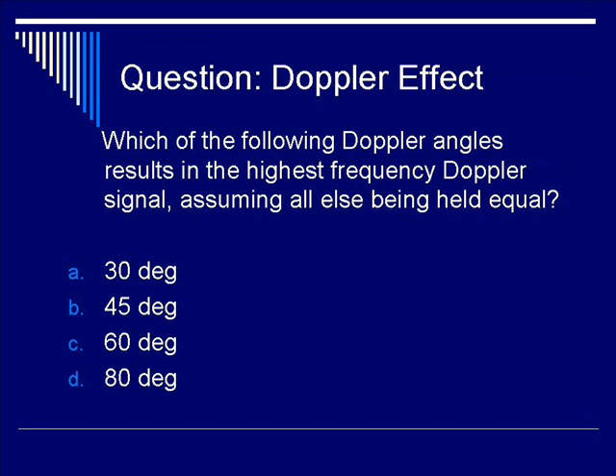Let's end this segment on a question: which of the following Doppler angles results in the highest-frequency Doppler signal, assuming all else being held equal? A: 30 degrees; B: 45 degrees; C: 60 degrees; or D: 80 degrees? The answer is A — 30 degrees — because cosine of 30 gives you the largest value for the cosine factor, which gives you the highest Doppler shift, all else being equal.